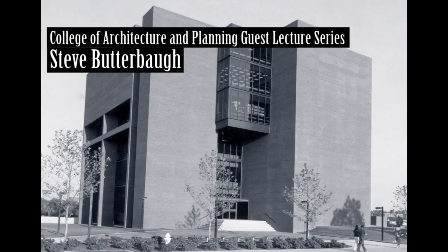These BTUs and kilowatt hours can be turned into dollar figures by converting the BTUs first to tons of coal or cubic feet of gas or gallons of oil, and then multiplying by the current price of the form of energy. In the Army project, where they were not concerned with such things as investments, meaning money at interest, and inflation, the operating savings is a simple multiplication of tons of coal or kilowatt hours times the cost of those fuels.